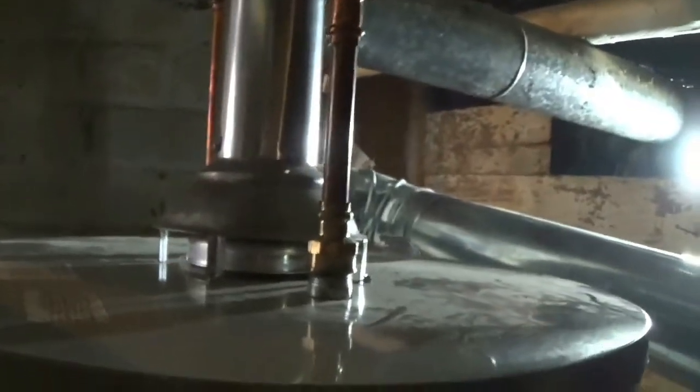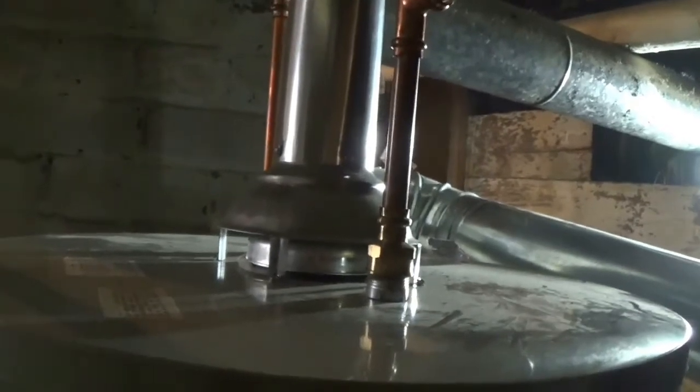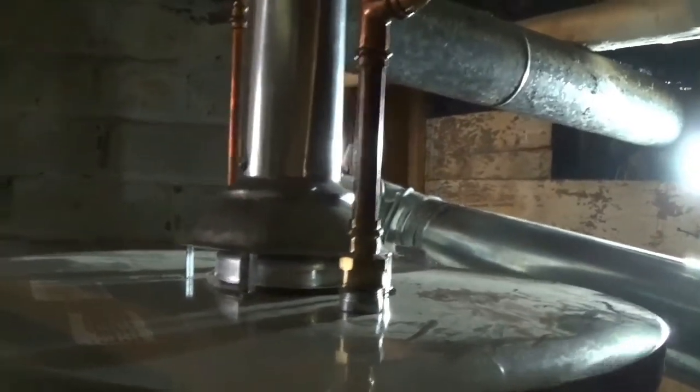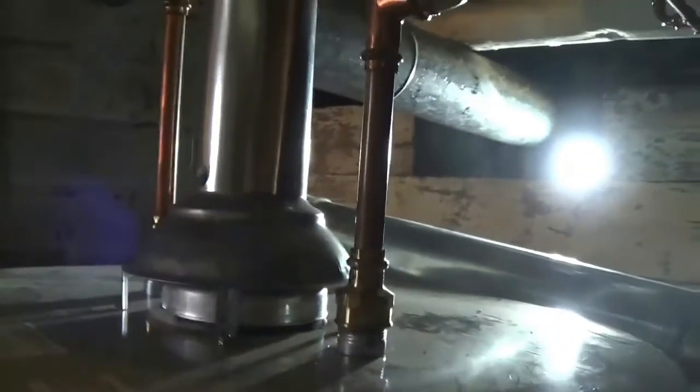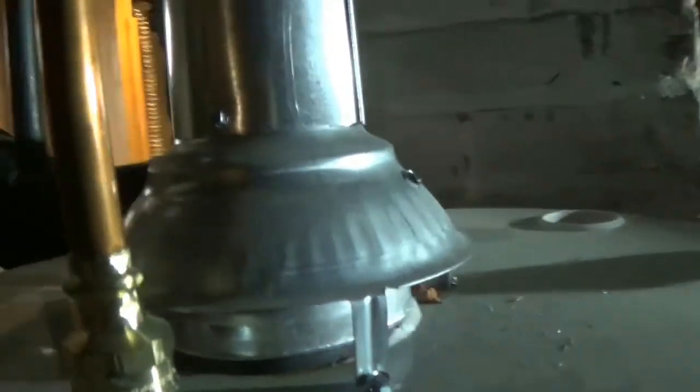So I'm going to say I'm circling no for that domestic hot water heater. There's a place on our sheet where we circle the no. Now, in order for it to pass spillage, does it need to go all the way around 360 degrees? Absolutely. If you find that it passes everywhere but one corner, it's still a fail, right? So that's why you saw me go 360 degrees around.